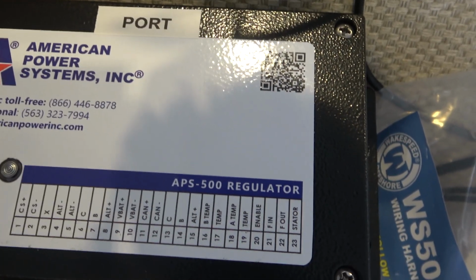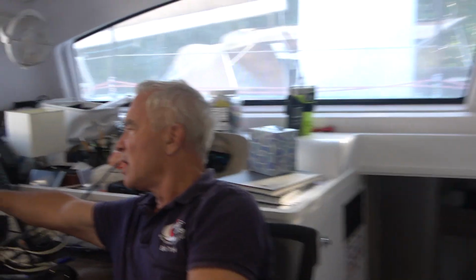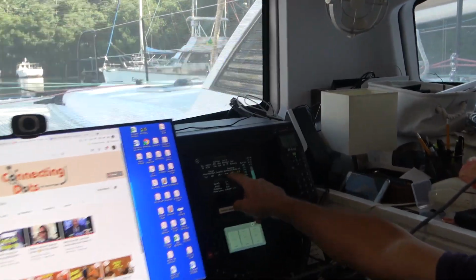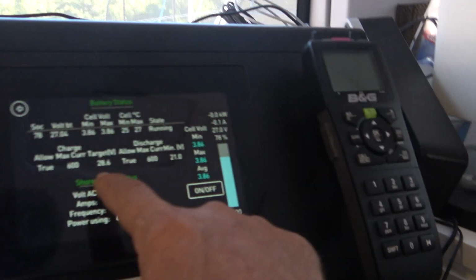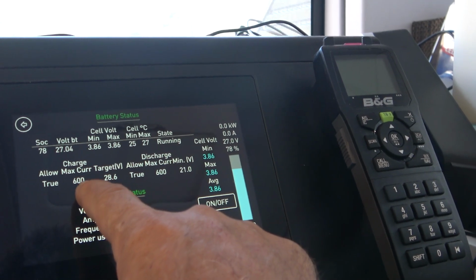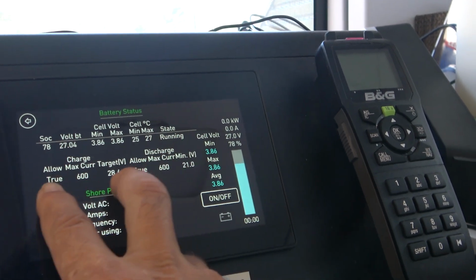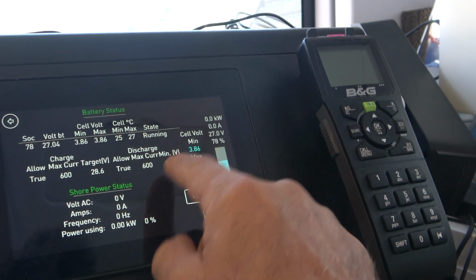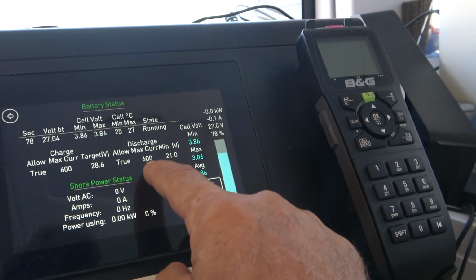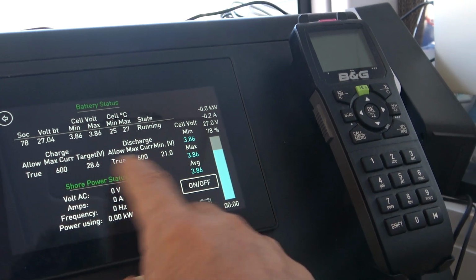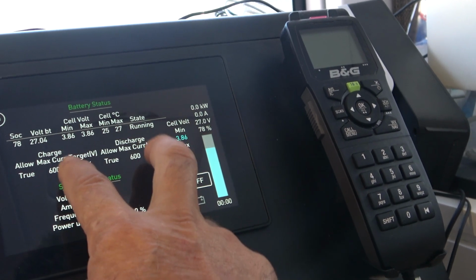What this does, basically, is listen to the BMS of the battery. The BMS sends a string of characters with the target voltage. Right now it's asking if it's charged. In charge mode, it asks for a target voltage of 28.6 volts and maximum amps of 600 amps, that's what this battery will accept to charge. To discharge, it will accept down to 21 volts and 600 amp discharge. So these are the charge and discharge limits of this battery.